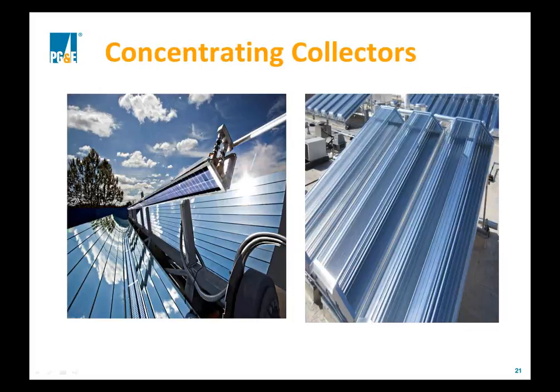These are likely not best suited for residential, but this is another type of collector that has received OG100 certification: concentrating collectors. In this slide, we can see hybrid PV and thermal collectors, of which the collector on the left is an example, generating electricity through the PV modules and capturing the heat through absorbers behind those modules, as well as thermal-only collectors like the one on the right. It uses a Fresnel-style lens to concentrate the sunlight onto an absorber and generate even higher temperatures. These are the types of collectors that would likely be used for high-temperature applications like solar thermal cooling with absorption chillers, or very high-temperature process heat applications. So again, probably not very suitable for residential.